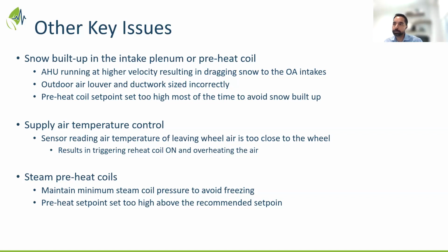No, that makes sense, and that's part of the next step, because first we analyzed what the actual problem is. So the next step, exactly to your point, is to understand what is fundamental. To me, there are two fundamental things: one is the design, and the second is the operation of the units at higher velocity, which is helping cause the snow to be brought in. If we slow down these systems to normal operating air velocity, we might mitigate half of that issue by just not bringing it in. Another thing is that some of these sites have predominant wind blowing in, so that's a consideration that should be made at the design stage. If your site has high winds, then you should consider putting additional factors into the design.